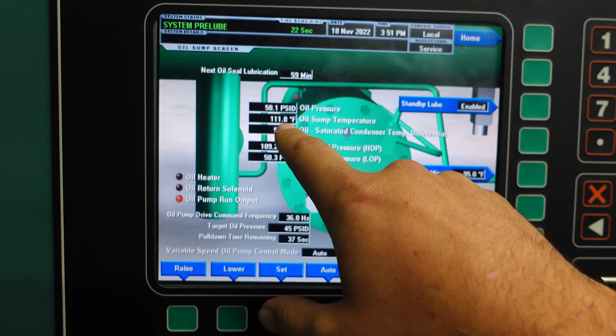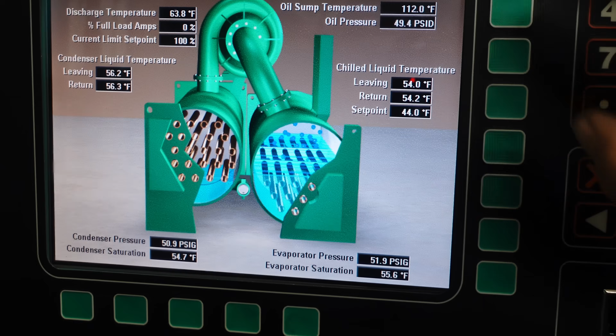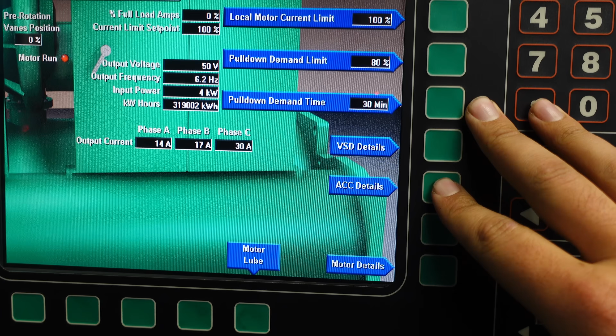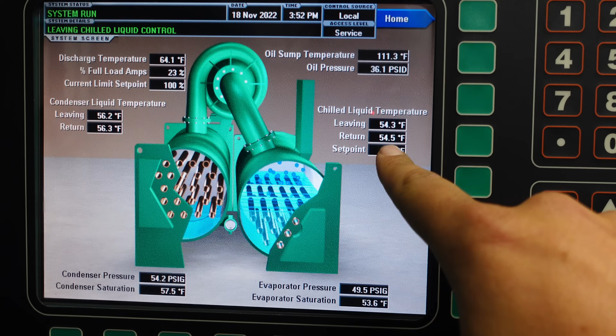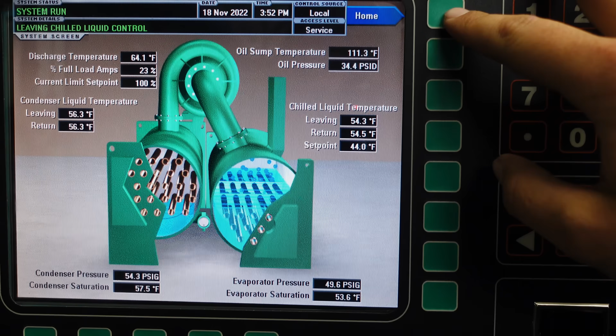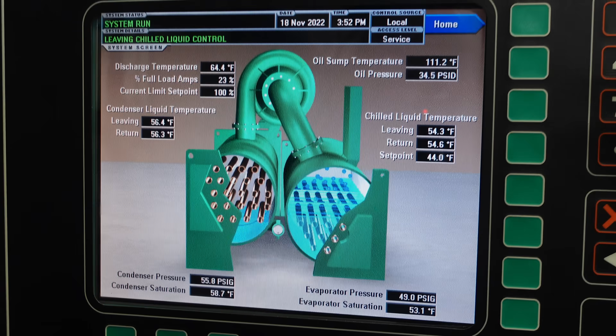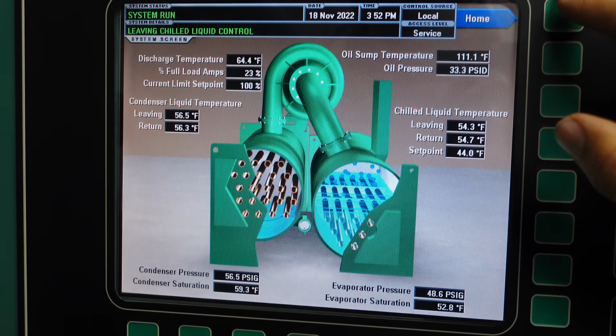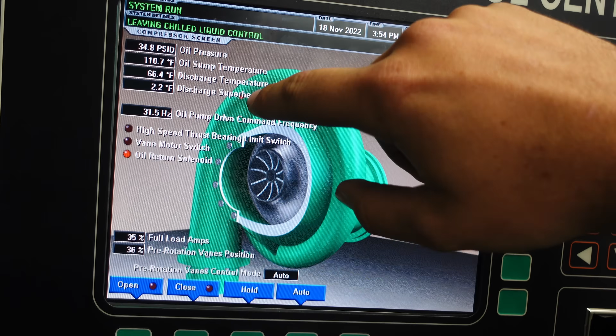Want to make sure that our oil temp stays up. Pump's running 32 hertz. We're starting to hone in on the set point there. Now we're starting to spin up. Little motor. Right now we got a decent enough load. We're gonna leave it at 44 set point. Our condenser water is really cold, but we've been flowing water on the condenser while we were doing the charging, so it's gonna have to heat that up, but shouldn't take very long, honestly. So we're looking fine so far.